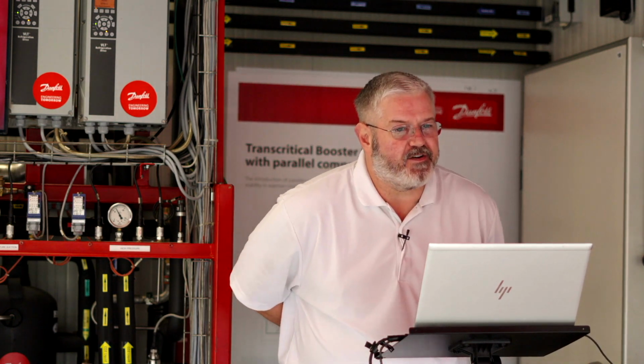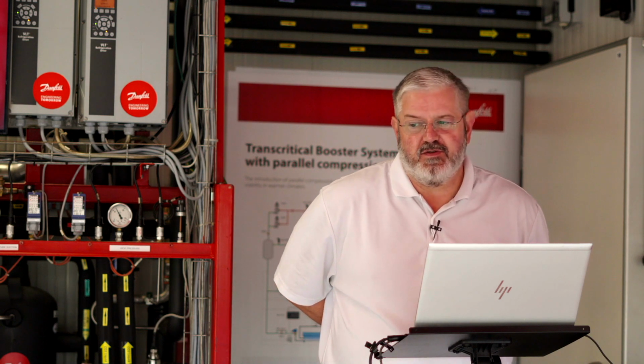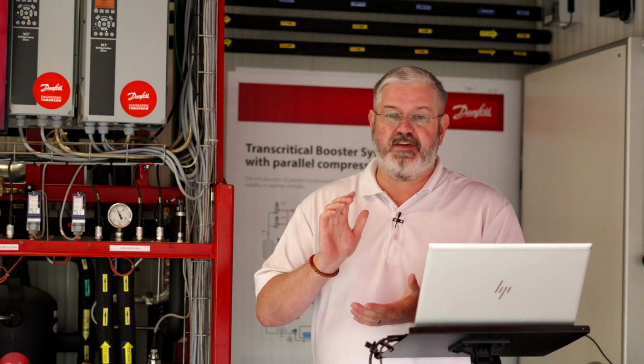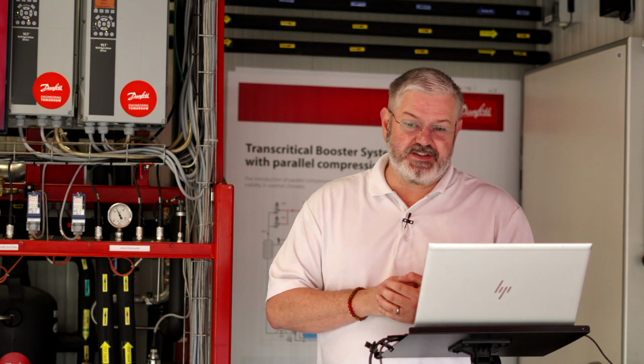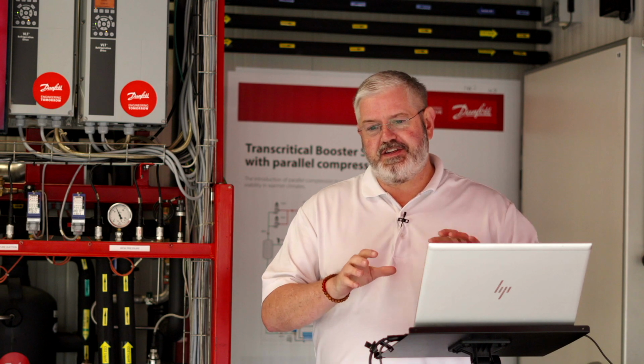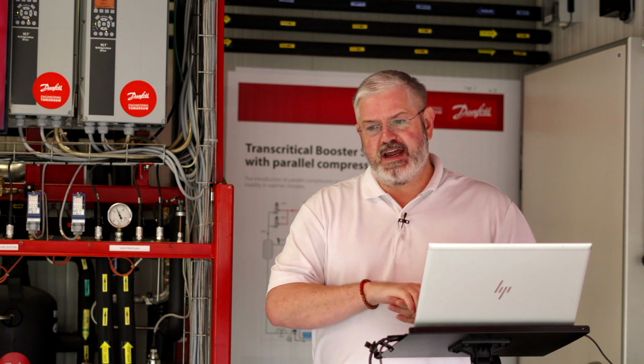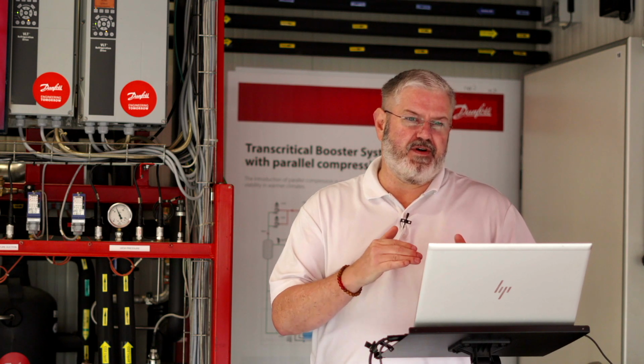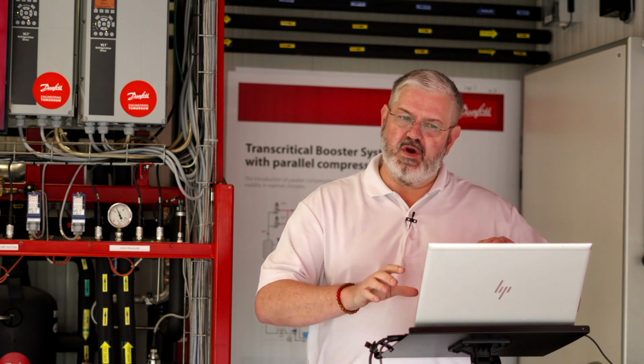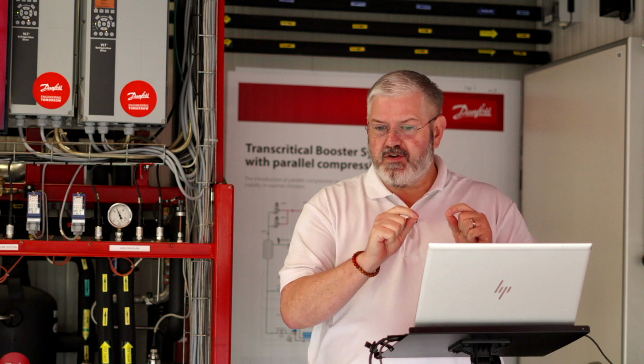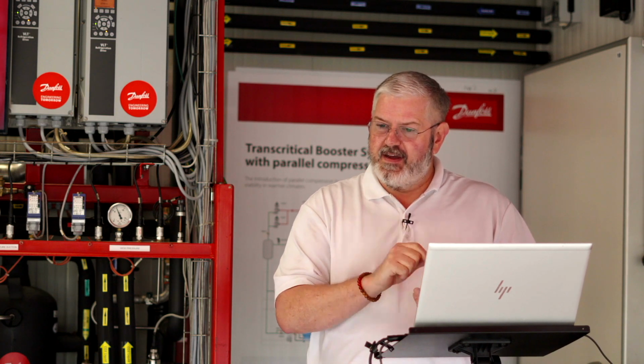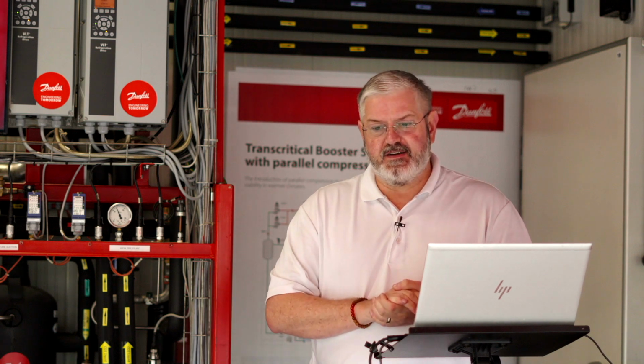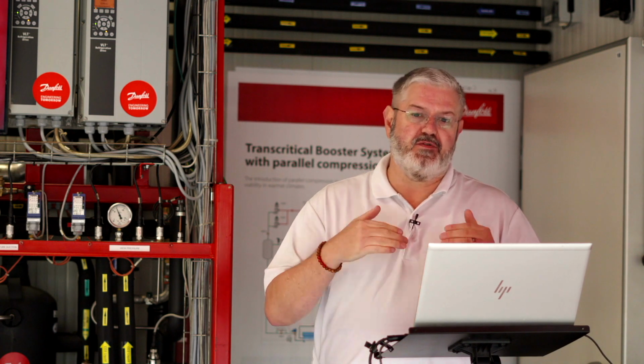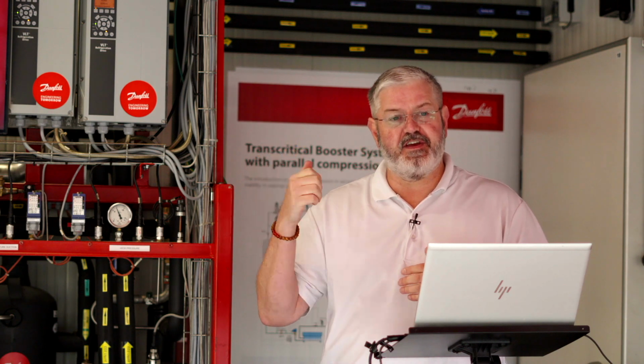Let's see. Actually, we got another great question. How do you avoid bursting the pipes? So with CO2, I got a question yesterday from the audience here at a training. They asked the question, can you keep your existing cases? Can you keep your existing field lines? And really the answer to that is no, because CO2 operates at much higher pressures. Your HFC piping is not going to be rated. Your low temp side of the system is going to have safeties on it at roughly 59 bar, some for 45 bar on low temp, but it's going to well exceed what you would have. So the shorter answer to your question is that CO2 requires thicker wall piping, more robust compressors. You avoid bursting piping because you have to replace it with piping suitable for the pressures that are experienced in situ.